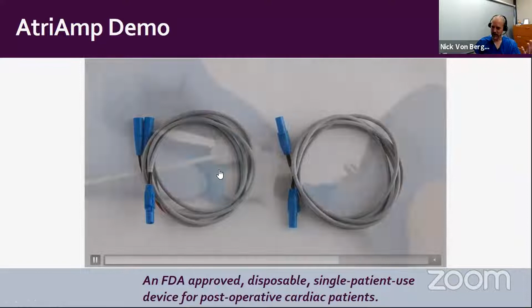So that very quick demonstration was how easy it is to now have the highest quality signals continuously in real time. So let's jump into what we do now, what is optimal, and how the AtriAmp helps. The highest quality signal recommended by the AHA is using an adapted atrial electrogram. Right now, we have to adapt a 12-lead EKG, but that's not continuous. It's not in real time. It doesn't have any of the advantages of the bedside monitor. The bedside monitor advantages include being continuous and real time, allowing me to look at it after the event has happened. And so the AtriAmp combines the beauty of those two things together to give us continuous real-time monitoring on the bedside monitor with all those advantages.